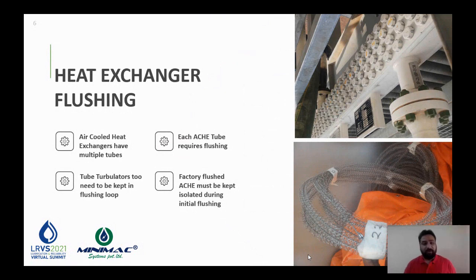Insufficient flow rate while flushing these heat exchangers might leave a lot of debris sitting inside the tubes. These tubes also have turbulators inside them with a certain mesh arrangement, and debris can get deposited in these turbulators. So it's important to remove the turbulators, carry out the flushing, and then reinsert the turbulators before going ahead for the final flushing.